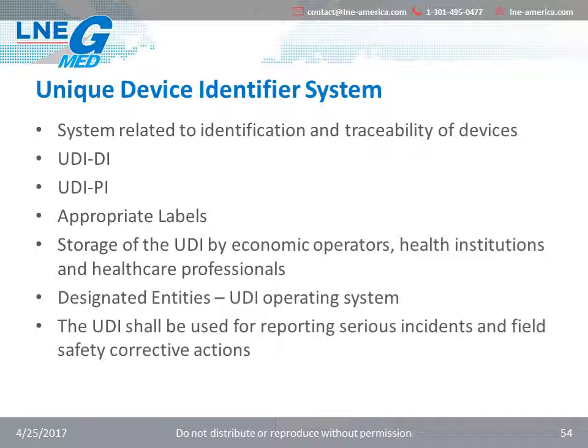So, for anyone that works under the current FDA regulation, the concept of UDI is probably nothing new. However, the concept of UDI is new to the European framework. The purpose of the UDI system is to establish a more functional system related to identification and traceability of devices. UDI will consist of the UDI-DI, which is specific to a manufacturer and a device, and a UDI production identifier, or UDI-PI, that identifies the unit of device production and, if applicable, the packaged devices.